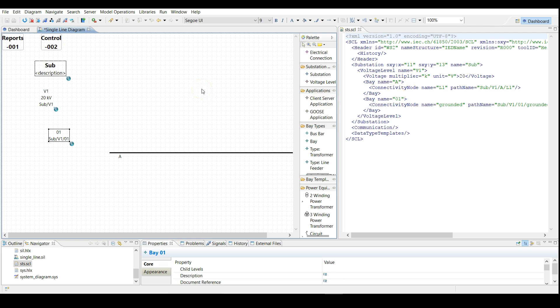What we are going to do is create three line feeder bays. To do that, choose the line feeder from the library, from the bay types tab. By using the library to create the bay, and not creating it from a default template, we will have access to specific functions for this type of bay.